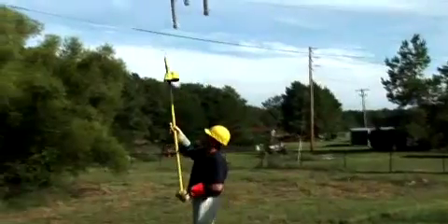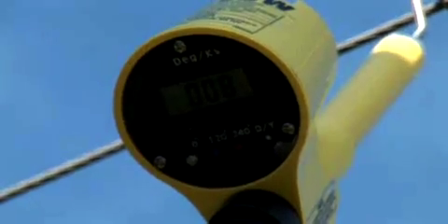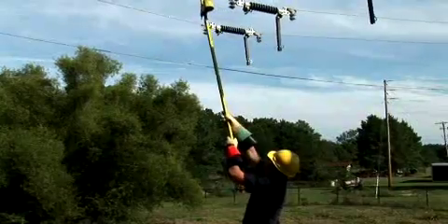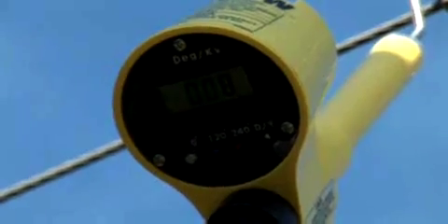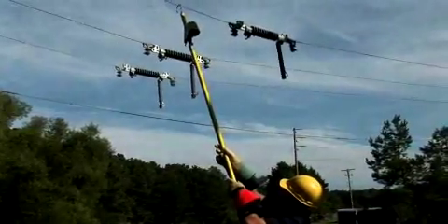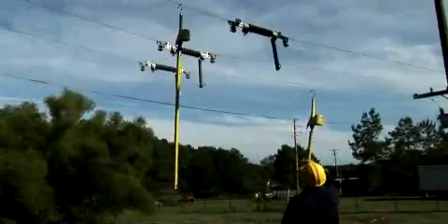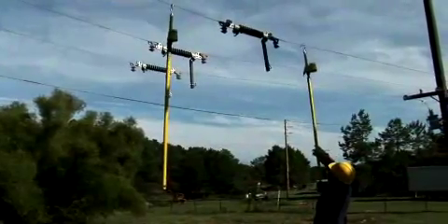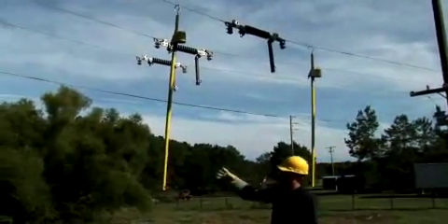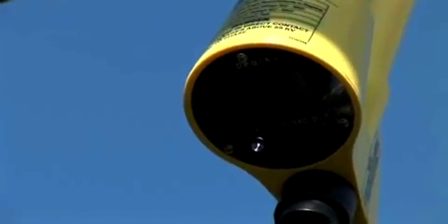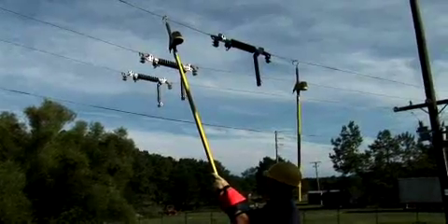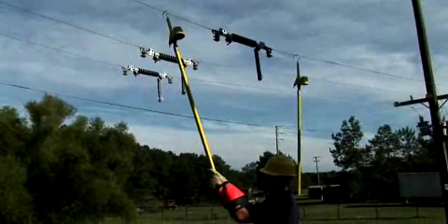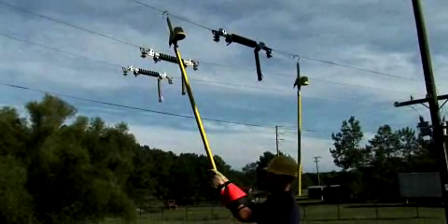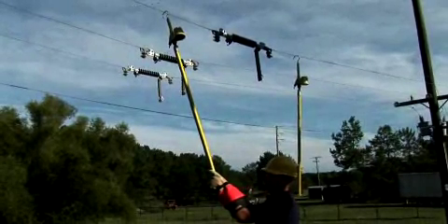I'm going to now move to the other side of the switch. I have 8 kV, 8 kV, and 8 kV here. Now I'm going to put my reference probe on this side of the switch and note the reading on the meter probe, and I read 0 volts with a white light. The white lights work independent of the voltage reading, so basically I have two readings telling me that I'm in phase. I can now close the switch.